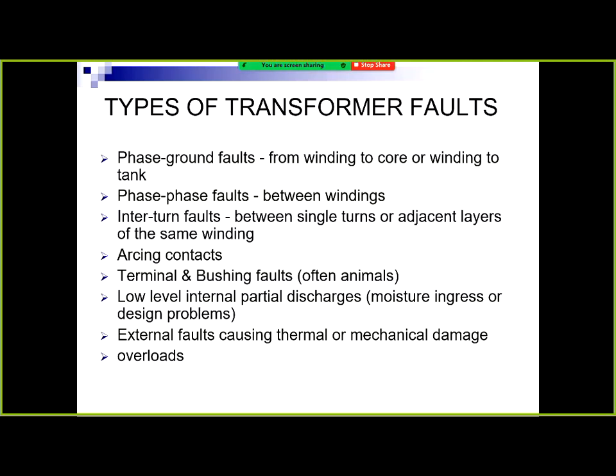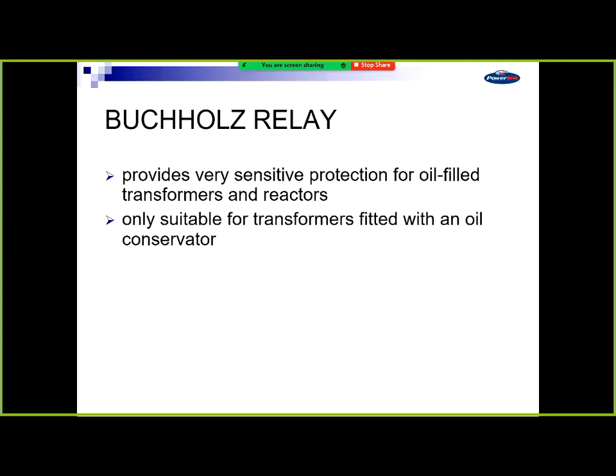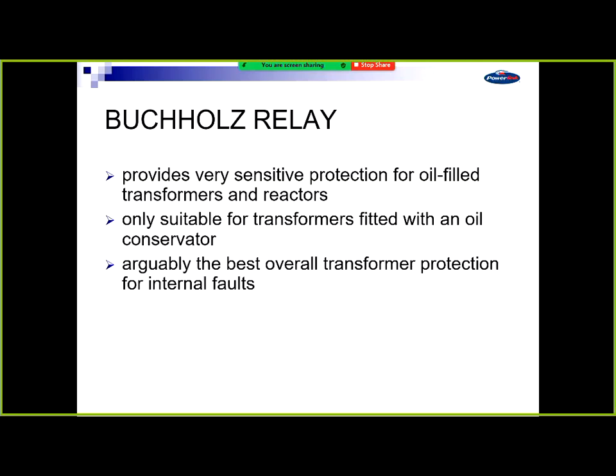Yeah, that's how I would put the order. A Buchholz relay is internal. It's part of the transformer that you buy. You've got to have a conservator for it to work. It provides really sensitive protection for serious internal faults. It will also cover you for low-level faults that keep going on that you can't detect. Into the winding fault that's just arcing, causing some gassing.